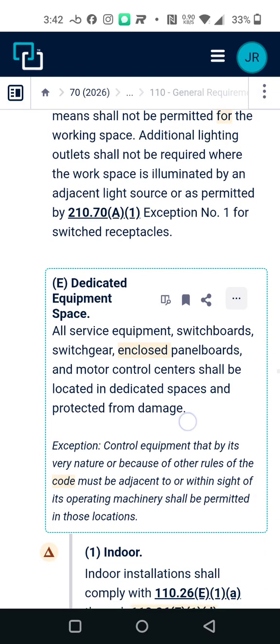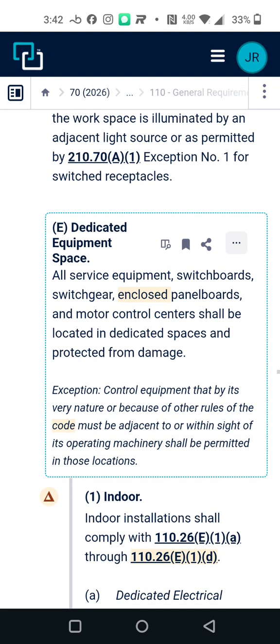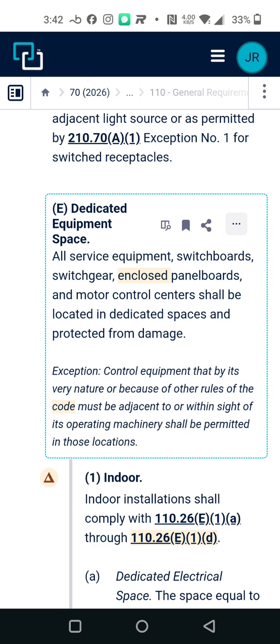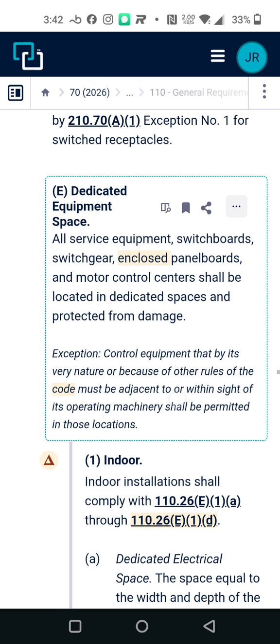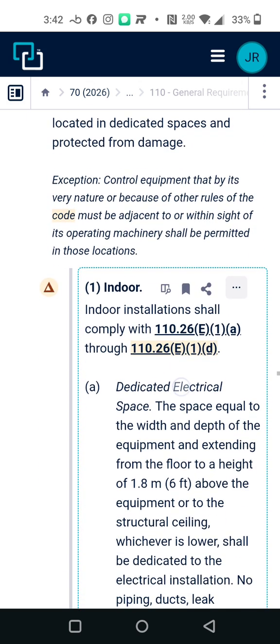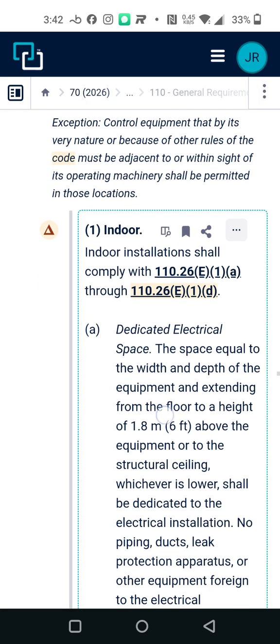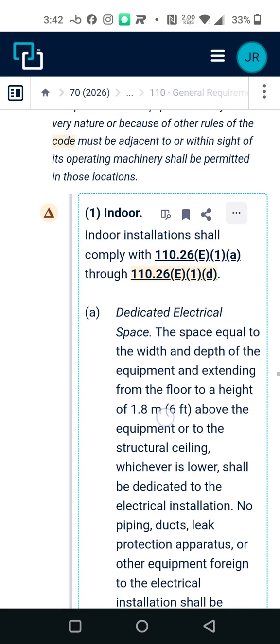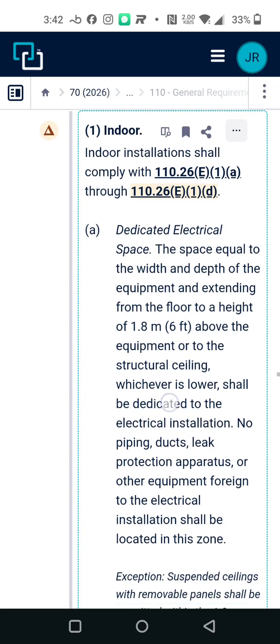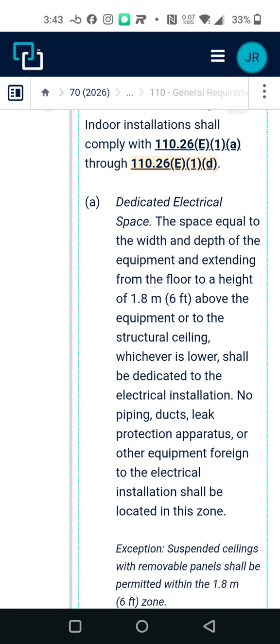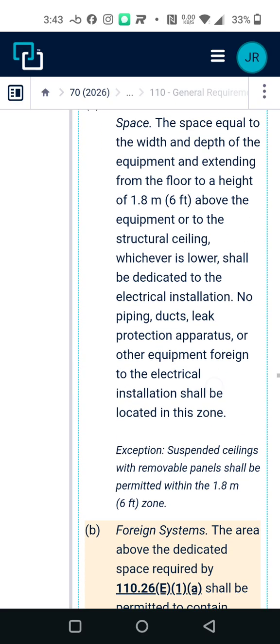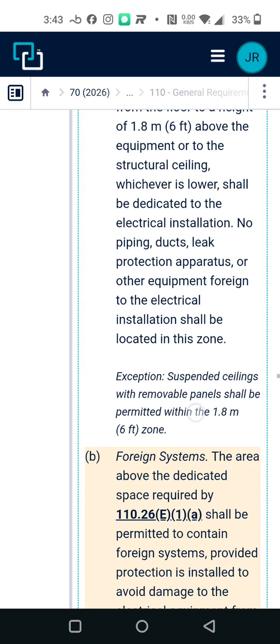Dedicated equipment space. All service equipment, switchboards, switchgear, enclosed panelboards, and motor control centers should be located in dedicated spaces and protected from damage. Indoor installation shall comply with 110.26(E)(1)(a) through 110.26(E)(1)(d). Dedicated electrical space is space equal to the width and depth of the equipment and extending from the floor to a height of 1.8 meters above the equipment or to the structural ceiling, whichever is lower, shall be dedicated to the electrical installation. No piping, ducts, leak protection apparatus, or other equipment foreign to the electrical installation should be located in the zone.